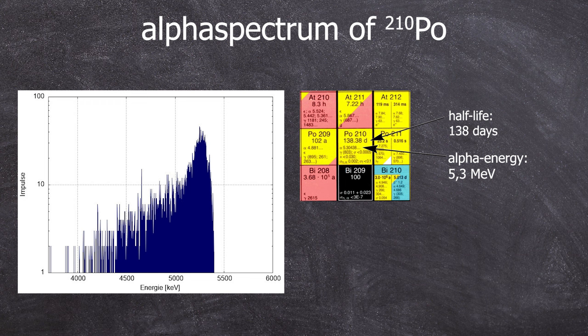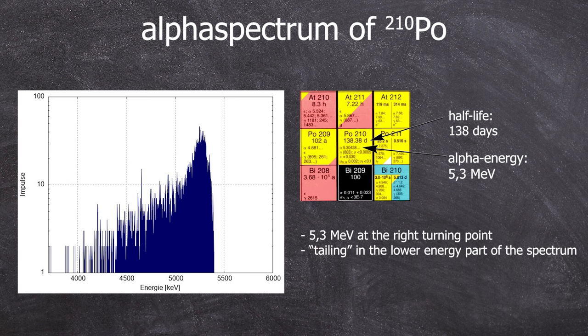Well, not exactly. It's the right turning point, but that's because the alpha calibration with alpha spectra is always done using the right turning points. And as usual, for every alpha spectrum, you can see the tailing in the lower energy range.